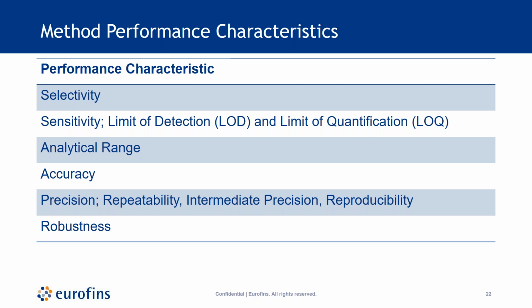How does the repeatability hold over multiple days, different instruments, different analysts, and that also ties into robustness. And robustness really can be expounded to mean a lot of different things. In a verification process, robustness may just be something where you have two analysts to make sure that in your laboratory both analysts can perform.